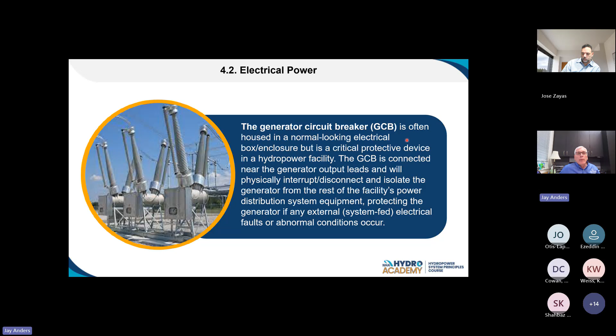One of the big things we talk about is arc flash. Maybe you've heard that before. What we want to do is, in the event of a failure, contain all that arc flash inside of a housing like this. And it's these generator breakers - racking them out, removing them, installing them - a failure could occur. There's lots of bus work inside of here, so we want to make sure that it's very safe.